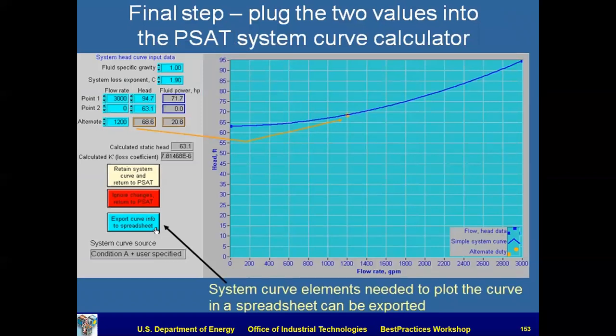This is from PSAT. So specific gravity 1, loss exponent 1.9. We put in the 3,000 GPM at 94.7. And by the way, it calculates the fluid horsepower. And then point 2 was the static head at 0 flow, 63.1 at 0 GPM. And you can put in an alternate point in here and it just puts a dot. Like that might be a point you were interested in highlighting, and you can do a screen capture on this or whatever you want to do.